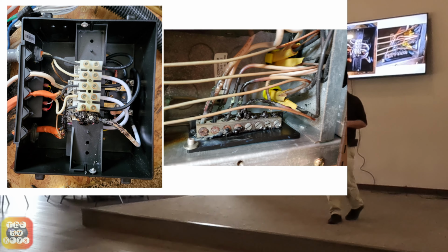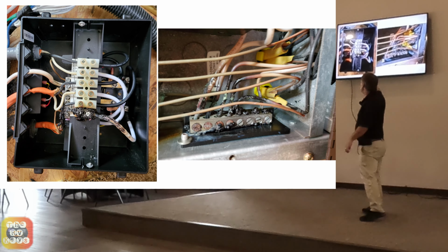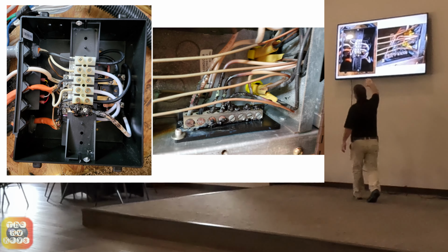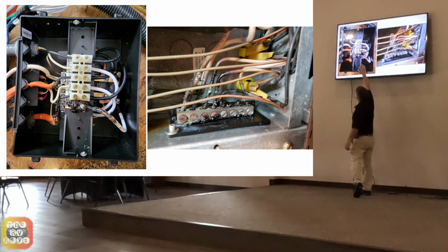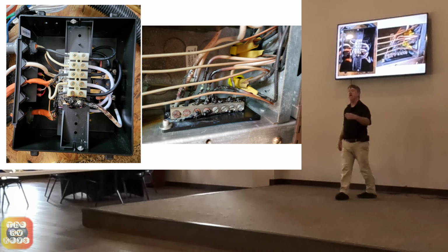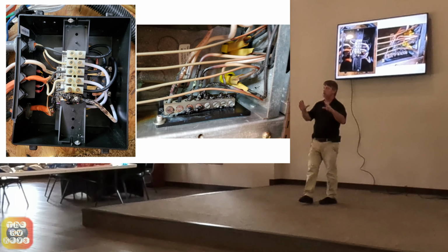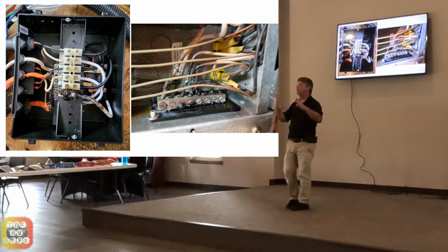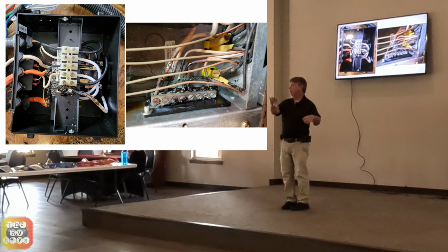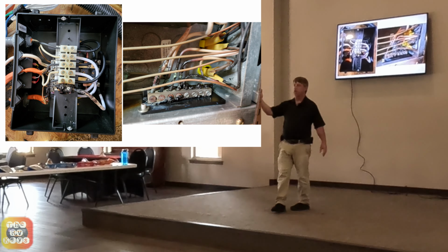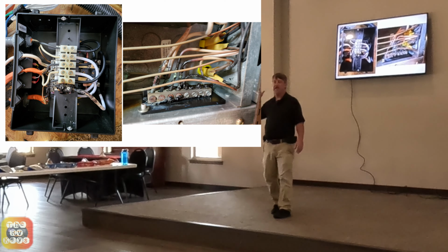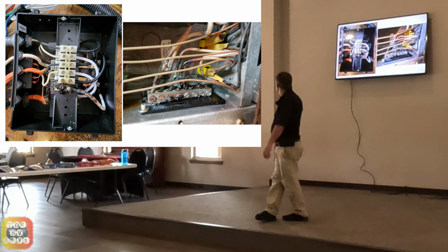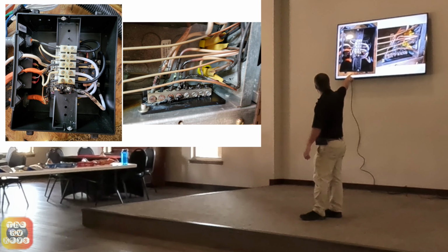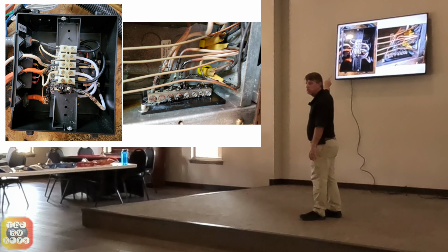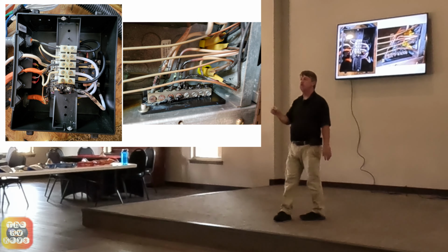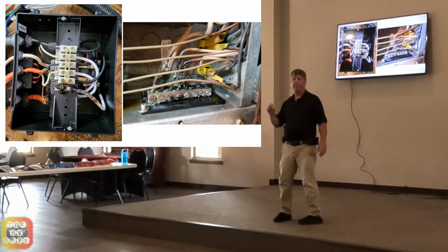It does happen. One of the first things I did when I opened this up, if you notice, the wire that's burnt in here is white. There's 2 more white wires. That's the neutral side of power. When you saw the circuit breakers earlier, those are all on the black side of wiring. Circuit breakers protect the hot side of wiring, there's nothing to protect the white side. And that's why in the other picture, all those wires that are kind of brownish used to be white. That's because the white wires heat up and cool down over time.